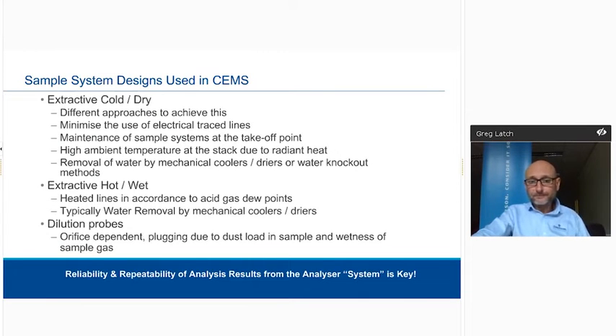Extractive hot wet - heated lines in accordance to acid dew point issues, if there are any. Again, extractive hot wet is managing the sample from the takeoff point from a particulates point of view, elevated temperature, all the way down through to either locally close coupled analyzers at the takeoff point, or typically off to safe areas down on ground level or better access points at the analyzers. Typically there's water removed in the traditional hot wet formats, by mechanical coolers and dryers.